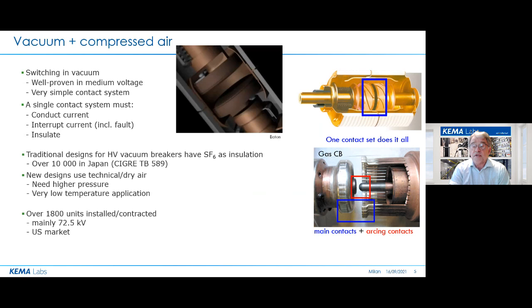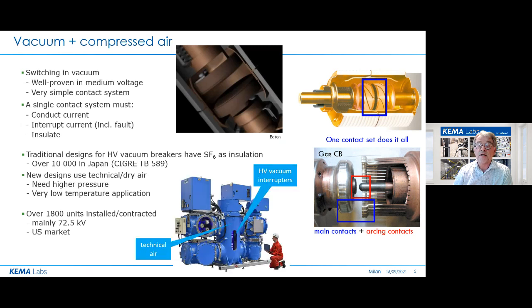But since 2010, also compressed air is becoming in use as outside insulation of the vacuum bottles that you can see here. Well, having compressed air means you need a higher pressure to deal with the dielectric requirements, but it also enables a very low temperature application. Well, these days, over 1,800 installations have been or are going to be commissioned, most in the United States and in the range of 72.5 kV. Well, here you see a picture of a modern 145 kV GIS.